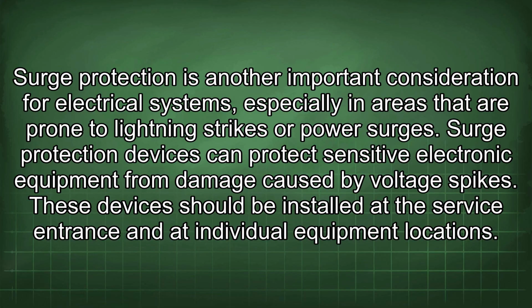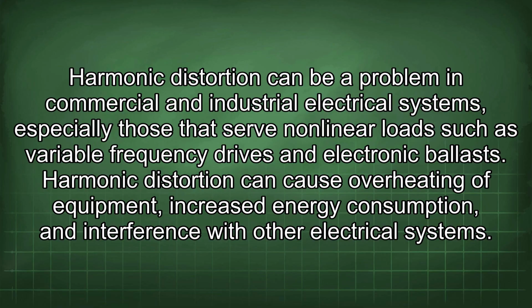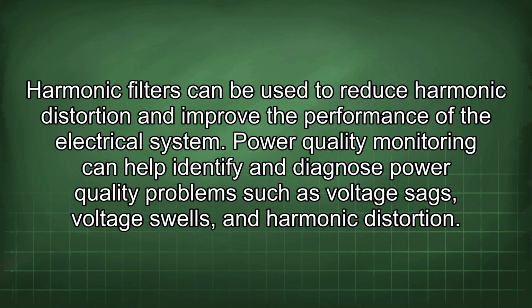These devices should be installed at the service entrance and at individual equipment locations. Harmonic distortion can be a problem in commercial and industrial electrical systems, especially those that serve nonlinear loads such as variable frequency drives and electronic ballasts. Harmonic distortion can cause overheating of equipment, increased energy consumption, and interference with other electrical systems. Harmonic filters can be used to reduce harmonic distortion and improve the performance of the electrical system.